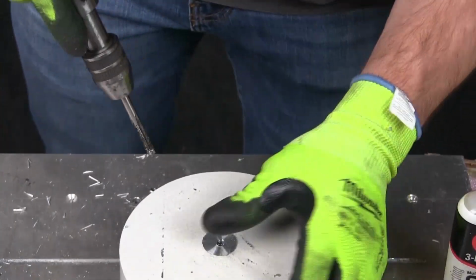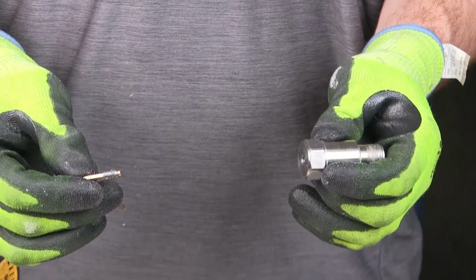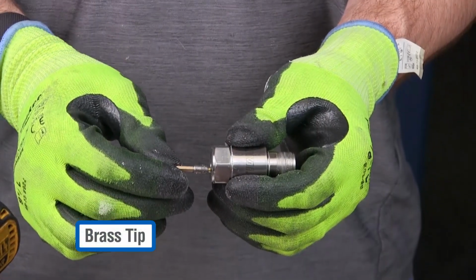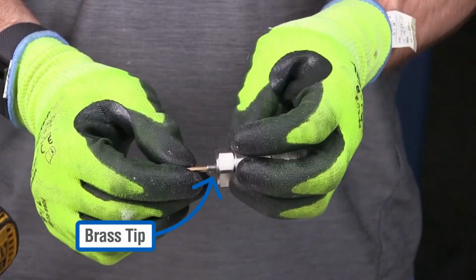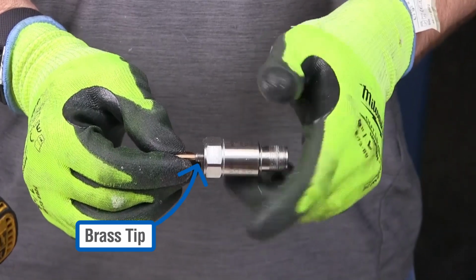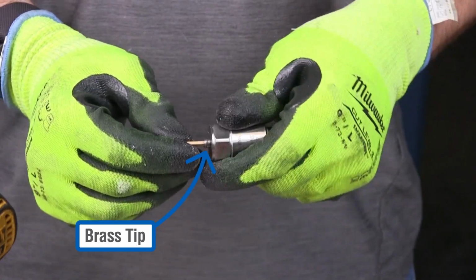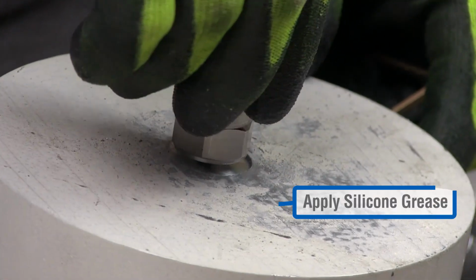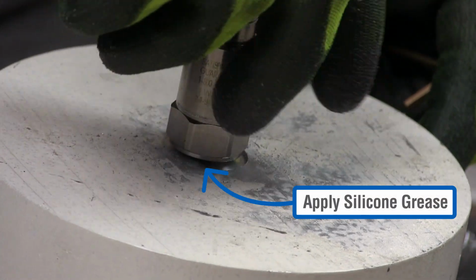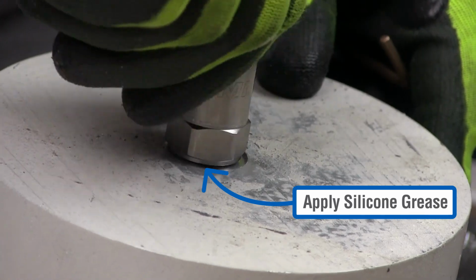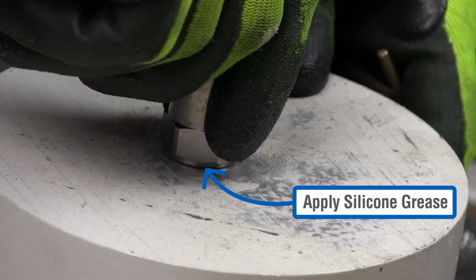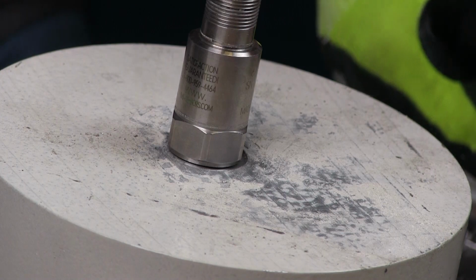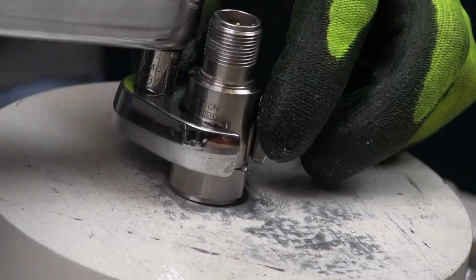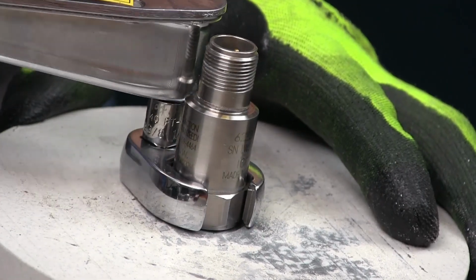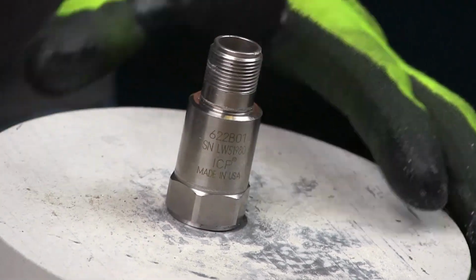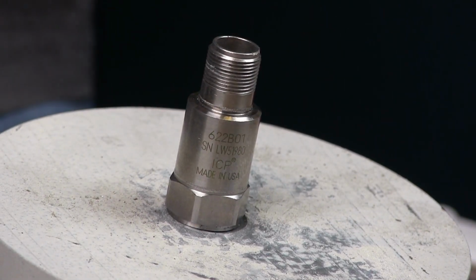When installing the mounting stud into the bottom of the accelerometer, be sure the brass tip goes into the bottom of the sensor. The brass tip is designed to collapse in situations where the accelerometer is over-torqued. This prevents damage to the accelerometer. Next, after some silicone grease is applied to the bottom of the accelerometer, it is tightened by hand into the newly tapped mounting hole and torqued to 2 to 5 foot-pounds or 3 to 7 Newton meters. Silicone grease allows for good mechanical coupling and superior accuracy when reviewing high-frequency vibration data.